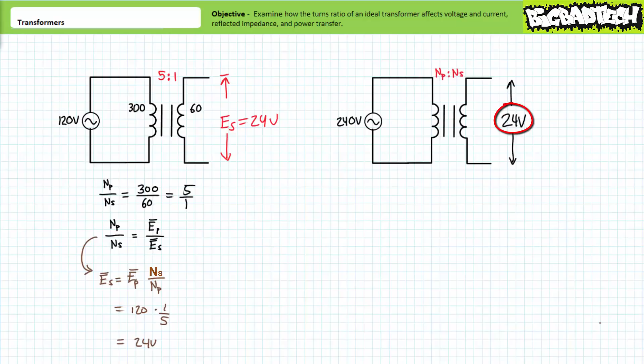By simply adjusting the turns ratio of the transformer, a manufacturer could make this device available for a number of different primary voltage levels. Consider this same device necessitating a secondary output of 24 volts AC, however being operated at an increased primary voltage of 240 volts.